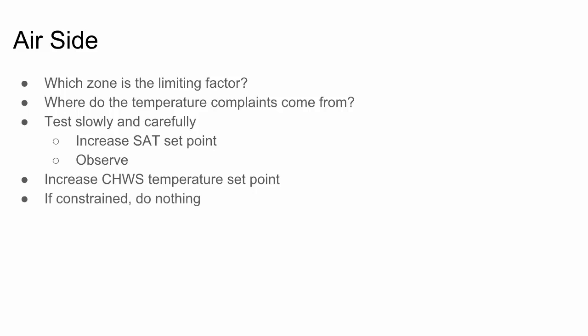So at this point we're going to take one of two directions. If it's constrained, if there's a zone that prohibits us from increasing the chilled water supply temperature set point, then there's nothing we can do. We have to stop right then and there. Otherwise we will impact occupant comfort.